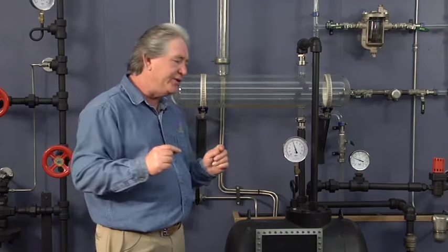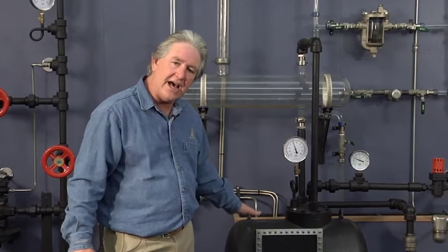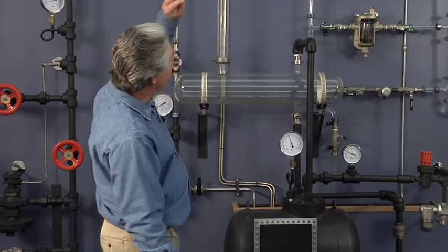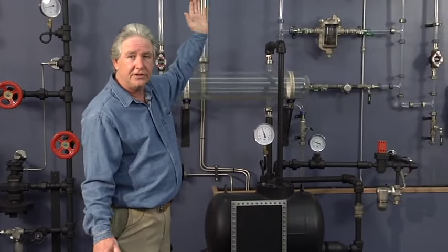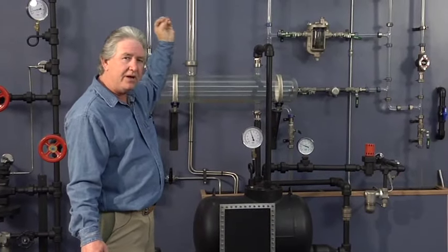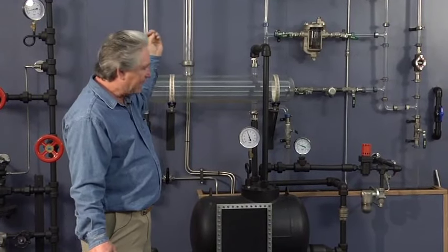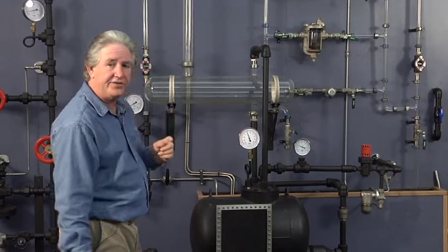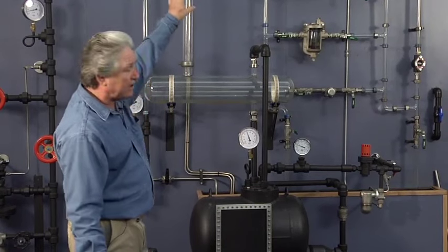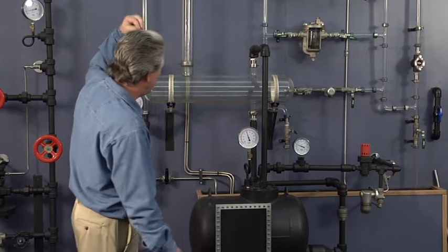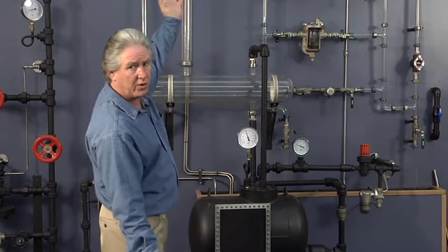If we engineer the downstream side of these exchangers correctly, we can ensure that we never corrode the tube bundles because we always keep the surface area dry on the exchanger. That's of very, very large value to all of our customers, regardless of the heat transfer setup, whether it's an air coil or a heat exchanger or a reboiler.